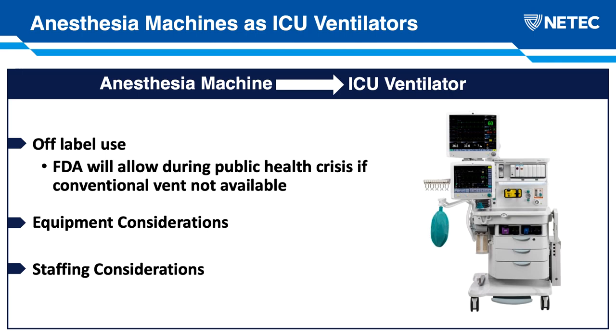I want to remind everyone that while using an anesthesia machine in a prolonged fashion as a substitute for an ICU ventilator is never our first choice, the FDA, in a situation where a hospital's available conventional ventilators were all being used and the need to ventilate patients exceeded the available supply of traditional ventilators, is allowing, during this public health crisis, the use of anesthesia machines in an off-label fashion. And they have committed to no enforcement action, and additionally have given guidance around some prolonged use of disposables and other components that typically would not be expected to be used for several days in a row. So I just want to stress that this is off-label guidance.